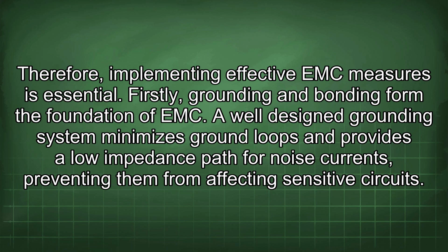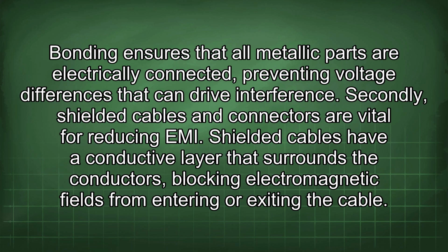A well-designed grounding system minimizes ground loops and provides a low-impedance path for noise currents, preventing them from affecting sensitive circuits. Bonding ensures that all metallic parts are electrically connected, preventing voltage differences that can drive interference. Secondly, shielded cables and connectors are vital for reducing EMI.